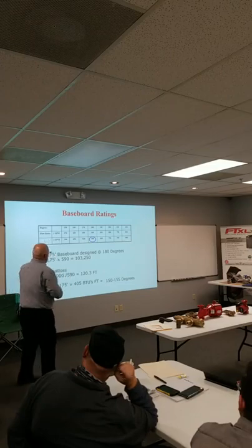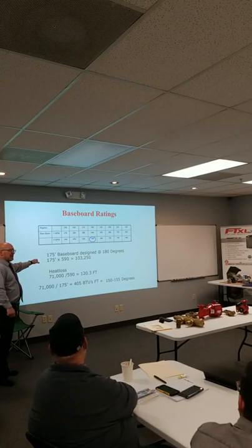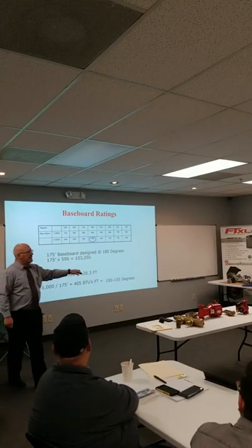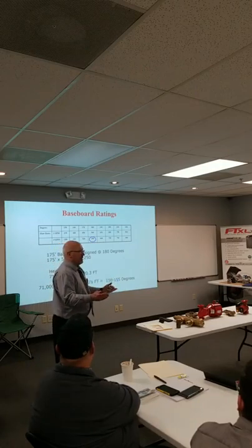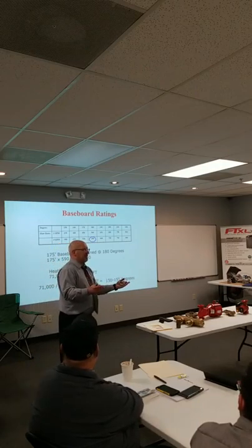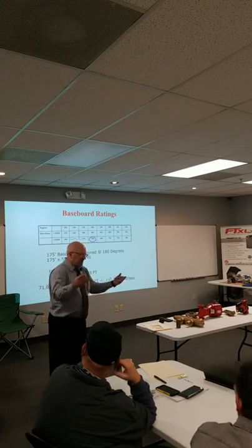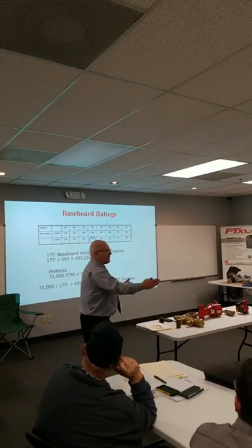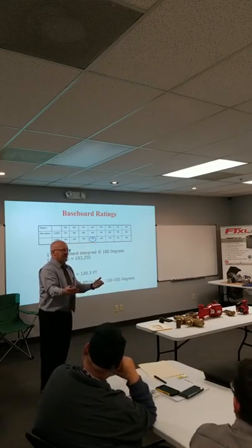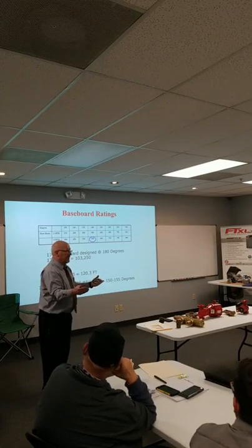Okay, so this is where we get the efficiencies. This is why I say do a heat loss and count radiation, because now you can go to Mrs. Jones and say, I've got two offers for you. I've got a cast iron 80% efficient boiler at, say, 90,000 BTU, whatever that 20% loss is. Let's call it 100,000. That's a little bit high. So a 90,000 BTU boiler. Or I'm coming in with a condensing boiler at 80,000 BTUs, which can be 95% efficient.